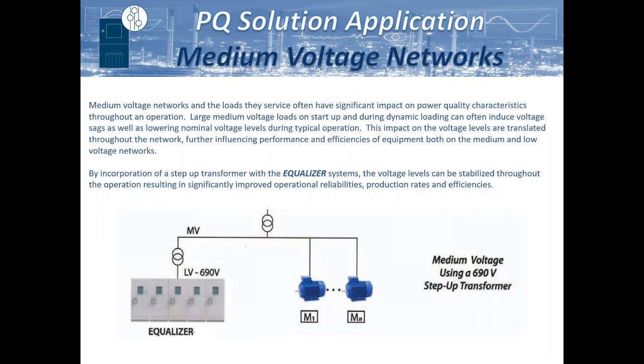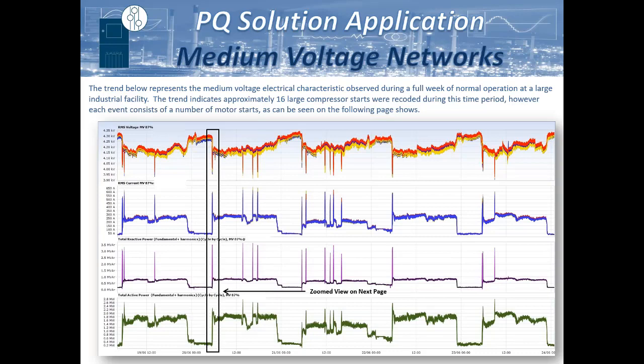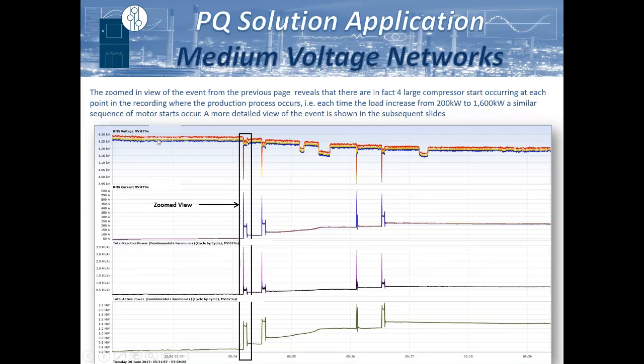So we just utilize a step up transformer. We can design the system at 600 or 690 volt, and then step that up to whatever level is necessary, whether that's 4160 or even at the utility sector as well, in order to better stabilize the utility network. You can see here, this is a large food processing facility. They had 16 large ammonia air compressors for their chiller operations. When we zoomed in, we could see that each one of those was actually four individual starts. And you can see that they were running a little bit high on a 4160 network in order to account for those voltage drops being induced. All of this was primarily attributed to the reactive power demand required in getting those motors started.